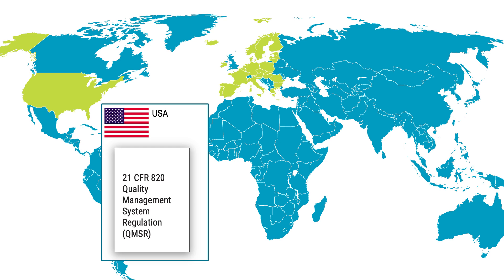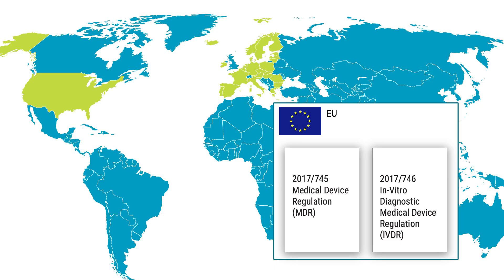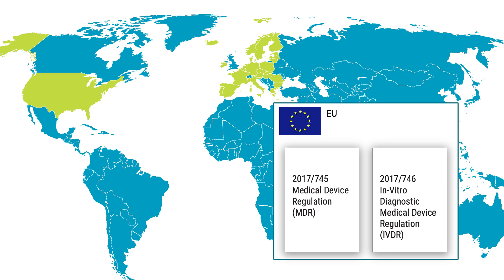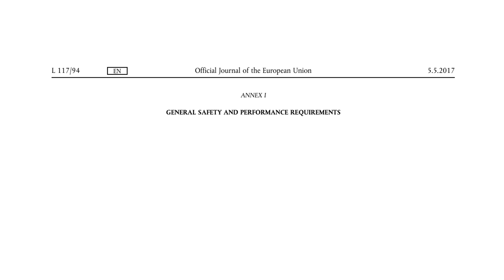Now let's turn to the EU. When placing a medical device on the EU market, one of two regulations will apply. The Medical Device Regulation, abbreviated MDR, covers regular medical devices, and the In Vitro Diagnostic Medical Device Regulation, called the IVDR, applies to In Vitro medical devices. The MDR and the IVDR require manufacturers to comply with safety, performance, and quality standards. Validating manufacturing processes is one way to fulfill safety and performance standards, as it ensures that these processes consistently meet the stringent requirements.